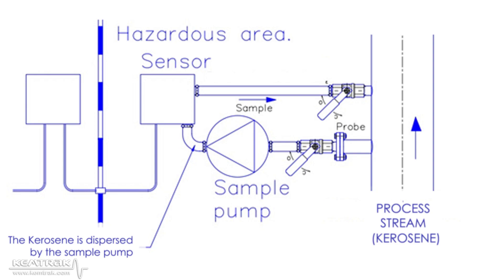For inline measurement, a turbulent flow rate with a high velocity is required to disperse the water in the kerosene. Typically, a turbulent flow greater than 1.5 m/s should be sufficient.